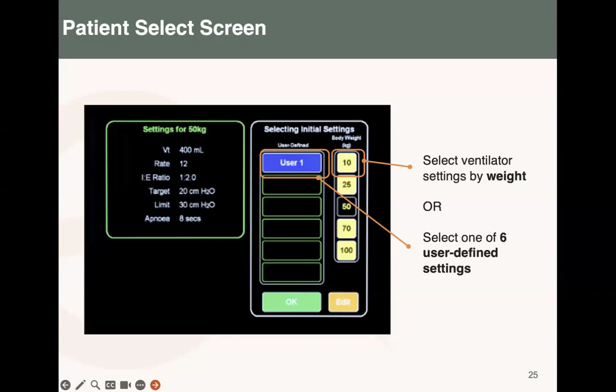So this is how it looks. As I said before, on the left side is the user setting. On the top one, these are the measured values. So always, when you use the machine, always compare. Even if an alarm comes on, before you panic, before you change anything, always compare what you have set against what is being measured.